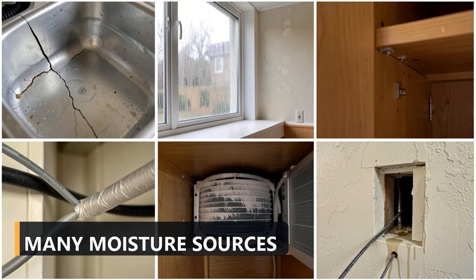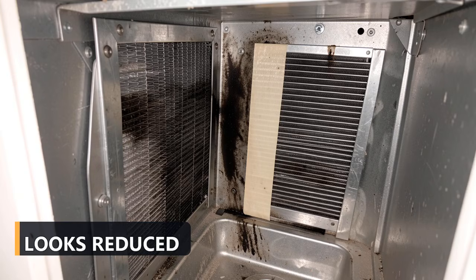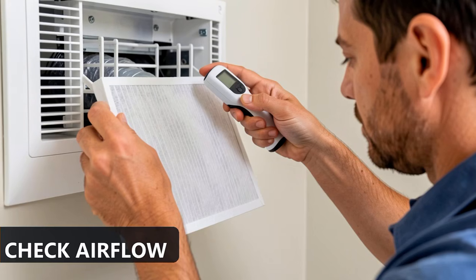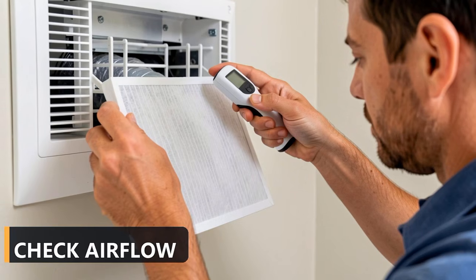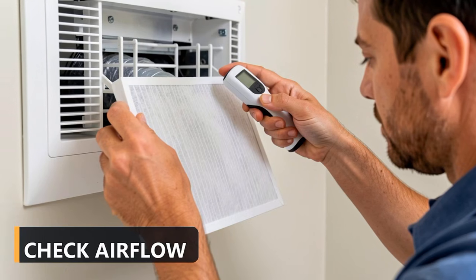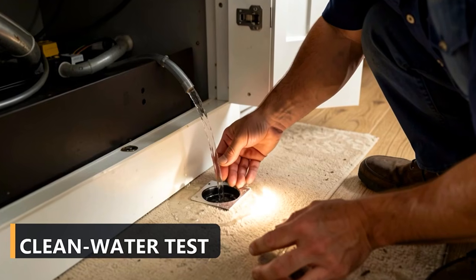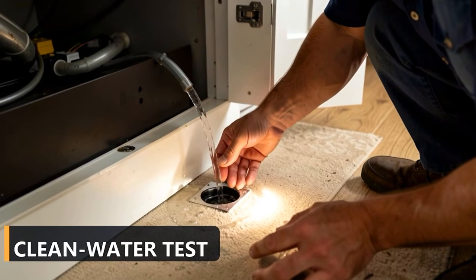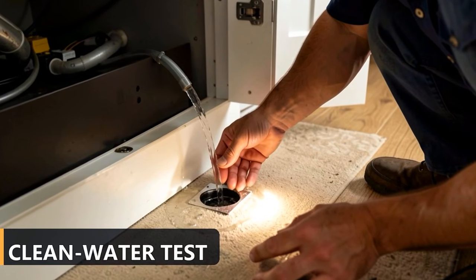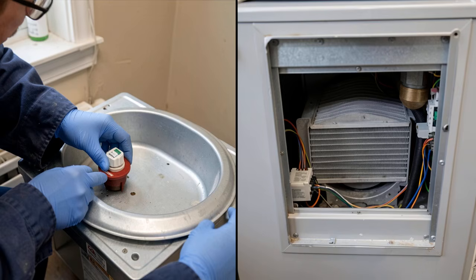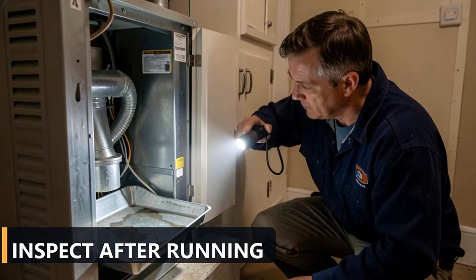After our treated coil and pan dry, the black surface looks reduced, but the system is not declared clean yet. Airflow is checked, the filter fits, the drain accepts clean water. The cabinet does not leak. The float switch works. The coil does not freeze. The system is allowed to run, and then it is inspected again for standing water and returning odor. That delayed test is far more meaningful than the original foam.